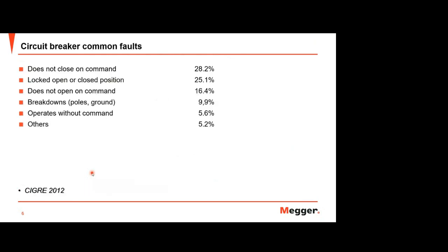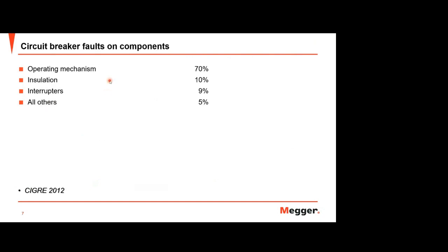Okay, this is just information based on the CIGRE 2012 report, with information on common circuit breaker faults. If you see here, three faults have a higher percentage in this report: does not close on command, locked in open or close position, and does not open on command. If you see more detail, these three are based on the operation of the breaker, or the mechanical side of the breaker, and give quite a high percentage compared to other faults like breakdown, insulation issue, operate without command, and others. And again, for circuit breaker faults based on component, as I mentioned before, the operating mechanism gives a higher level, up to 70% compared to other component faults.